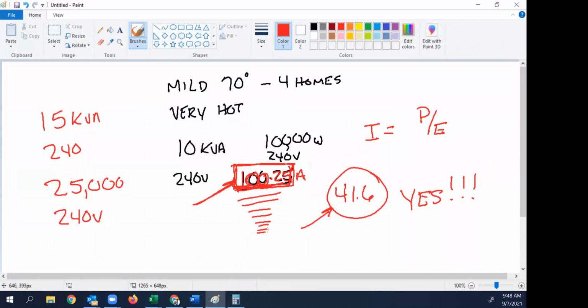Any questions there? You see how I did it? There's another way to do this if you want to use all math. What's 41.6 plus 41.6? Like 83.2, something like that. Okay, so I doubled my amperage here. When you do that, you can also double your kVA size. That 83 still doesn't meet 100.25. What's the next transformer up on the chart? 15, 25... yeah, 25 will do it.